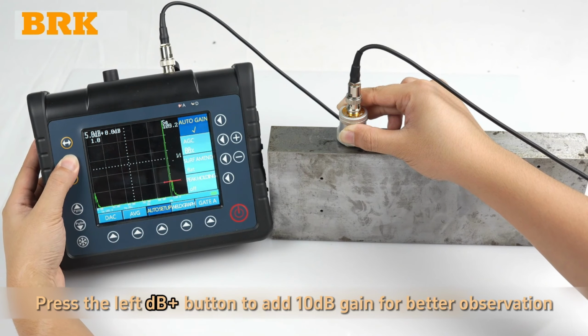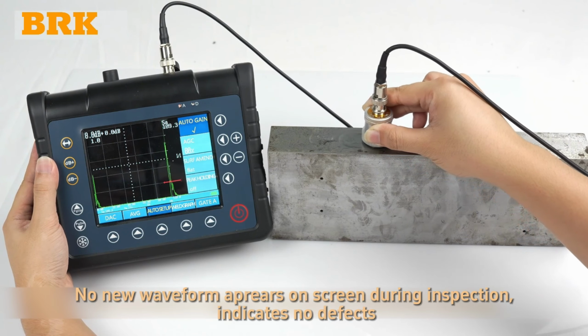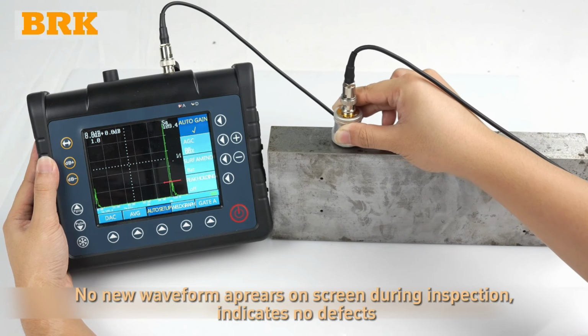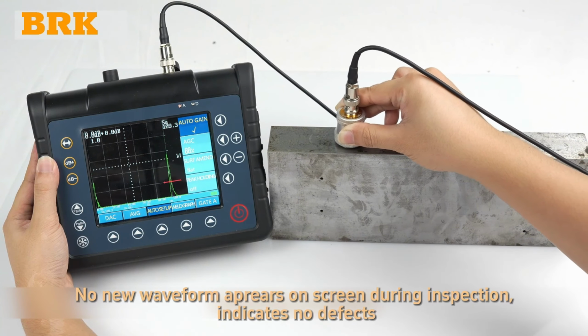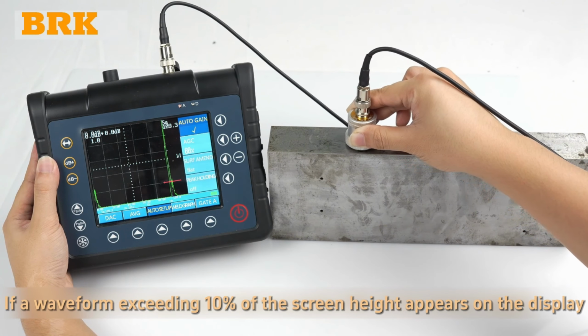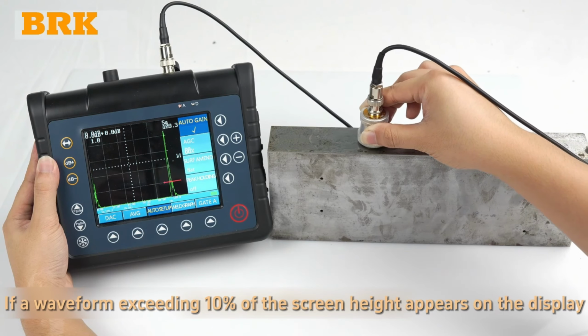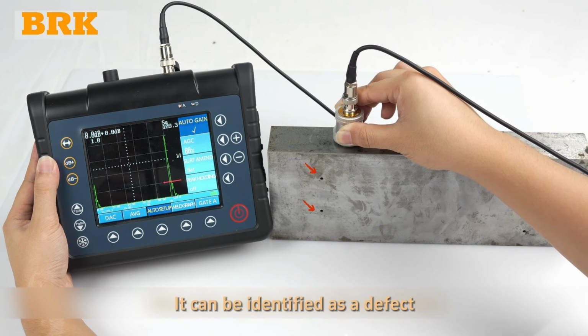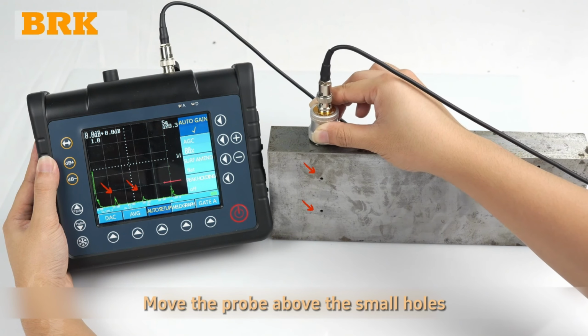Press the left dB plus button to add 10 dB gain for better observation. No new waveform appears on screen during inspection, which indicates no defects. If a waveform exceeding 10% of the screen height appears on the display, it can be identified as a defect. Move the probe above the small holes.